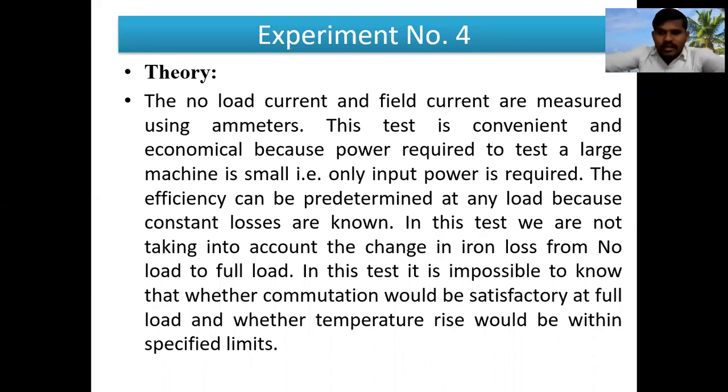So see, only the running test can be conducted, or only the no load test. So the power requirement for conducting this type of test is very small. So if it is a big size machine, it is economical, because the power requirement from the supply is less. While conducting these types of test on a big or large machine, it is economical. Or it is convenient, no complication is there.